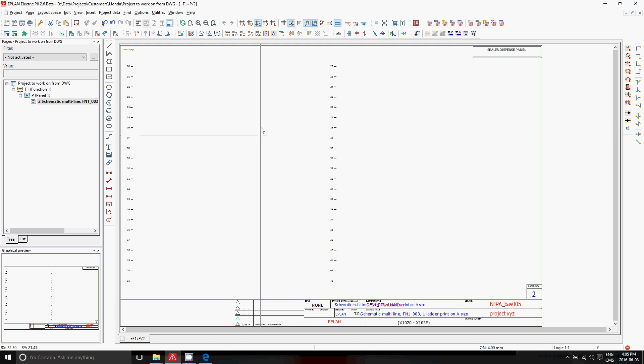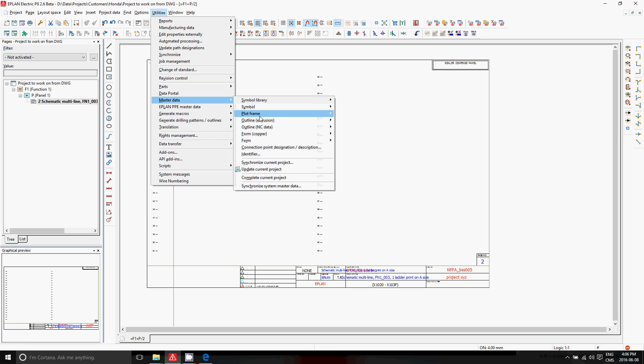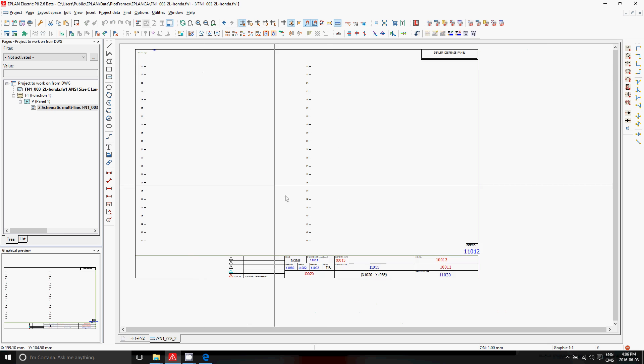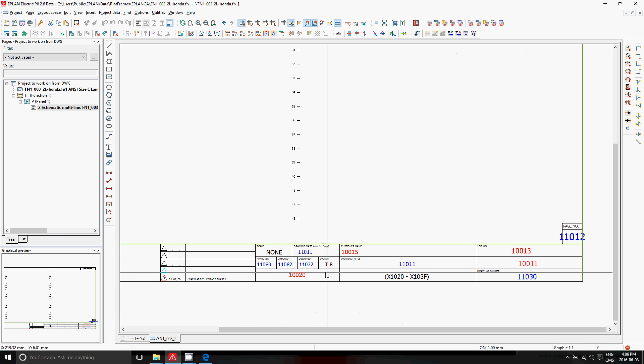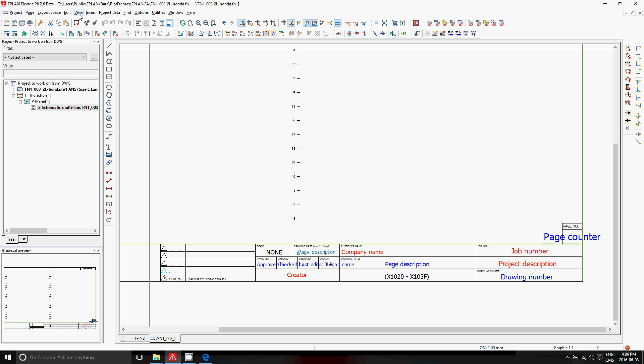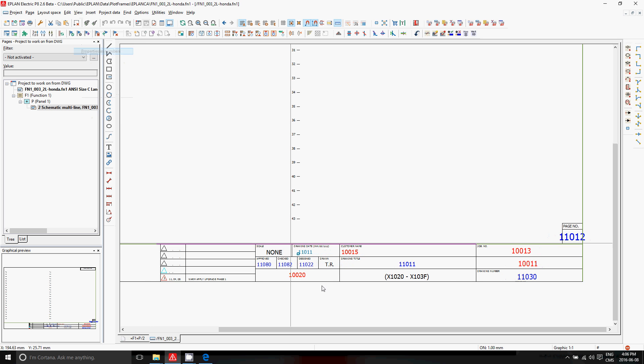The title block is something like this. Here I created a title block from a DWG file and just made it smart. I went to master data, plot frame, and created my plot frame here. Specifically, where you see these numbers — these numbers can be viewed as properties, numbers, or as descriptions — and they actually select here whether it's a page property or a project property. You can then specify what exactly it could be.